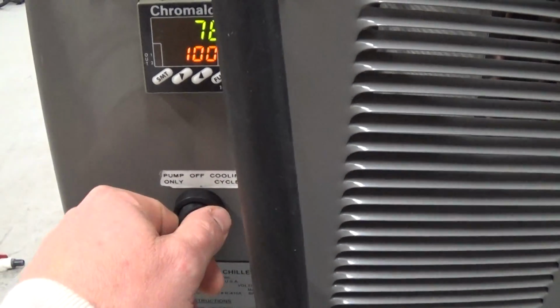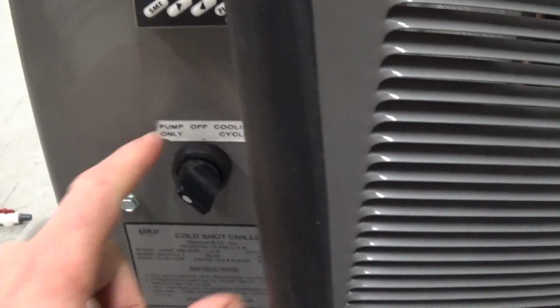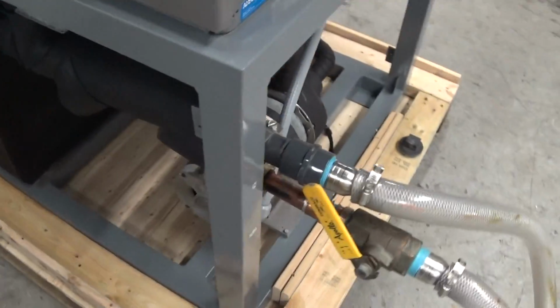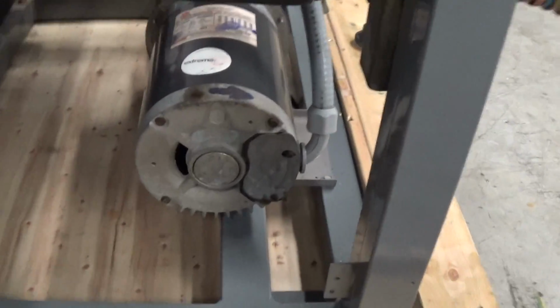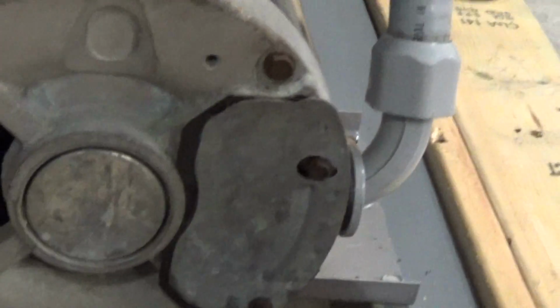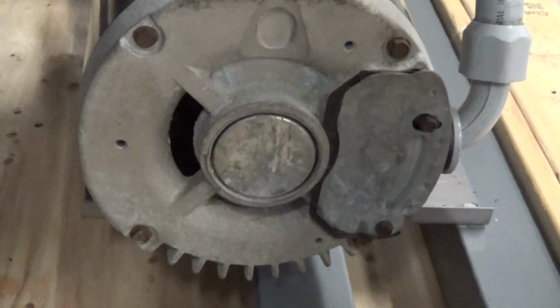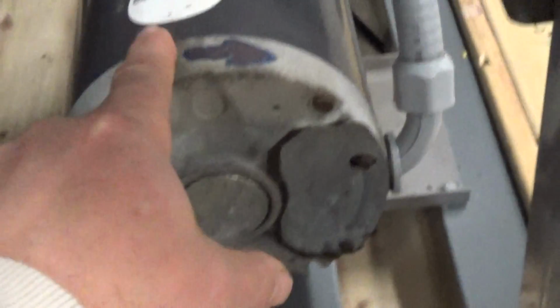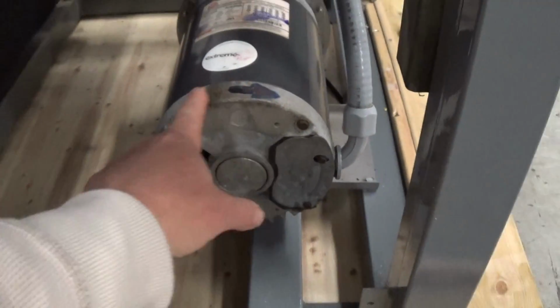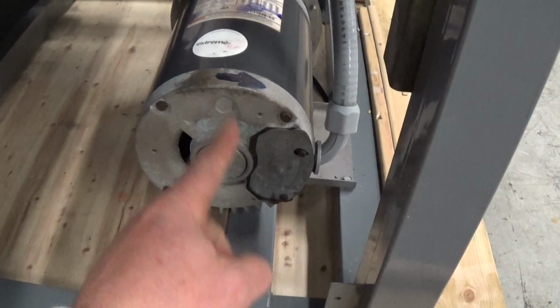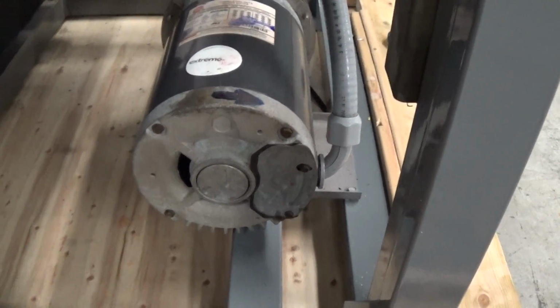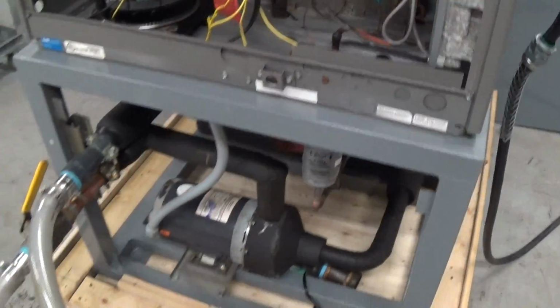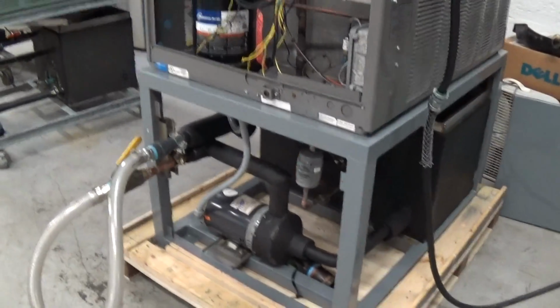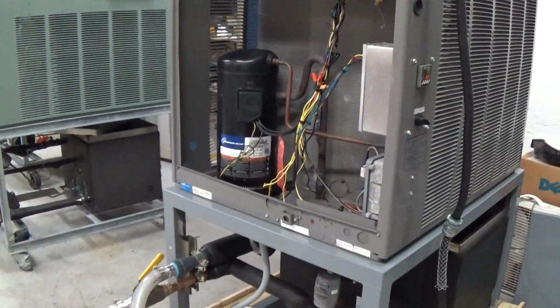So you're going to have somebody here, and they're going to toggle it to the pump only position just for a second. And while you do that, you're going to go down and have somebody look at this pump here and take off the end cap on the pump there, or you can actually look in there when you toggle the pump on and off and make sure you have the right rotation. There's an arrow here. Most pumps looking from the back end are clockwise, looking at the shaft end, as is this one here. So that's important, because you don't want to run the pump backwards. It will run backwards, but more importantly, you don't want to run a three-phase scroll compressor backwards.